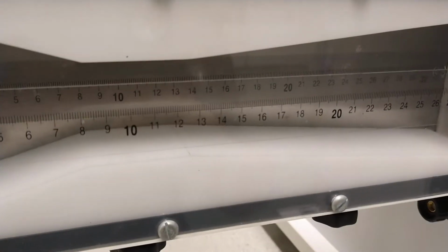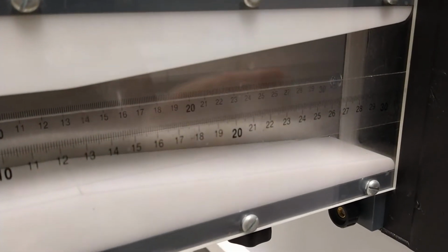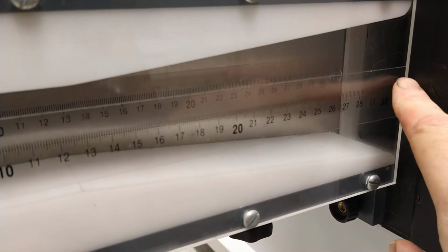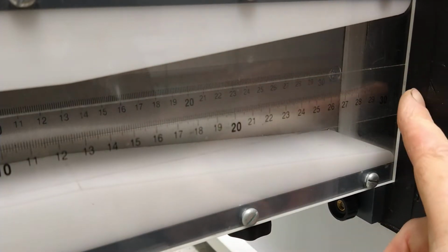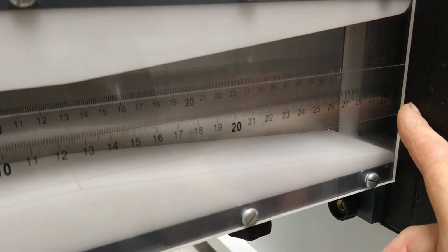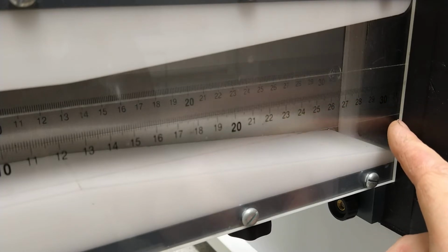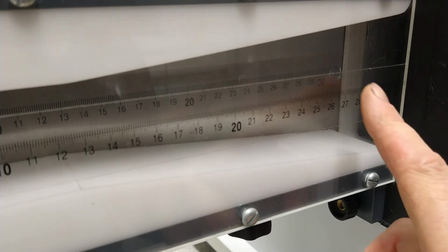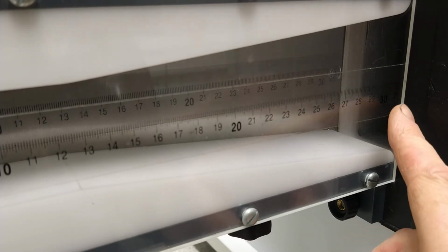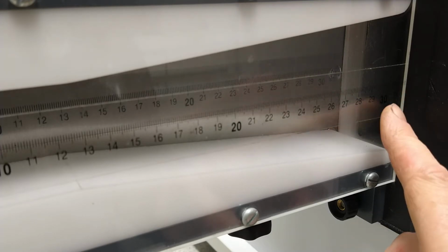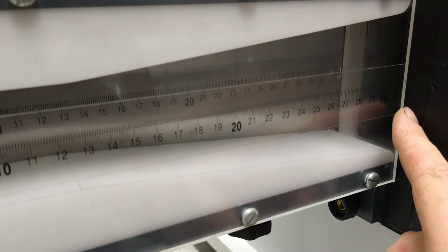What you find with a Venturi like this is that you have a certain volume of air exiting the plenum chamber. That will depend on the fan speed and so on, but you'll have a certain volumetric flow rate of air coming out here, so many meters cubed per second, or a certain mass flow rate, so many kilograms per second. That's a constant. So for a given fan speed, the flow rate of air coming out of this is a constant.